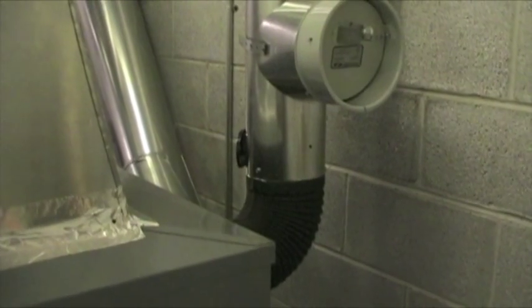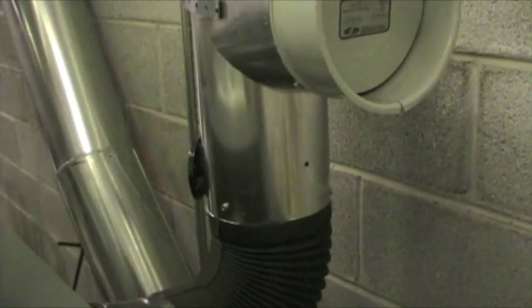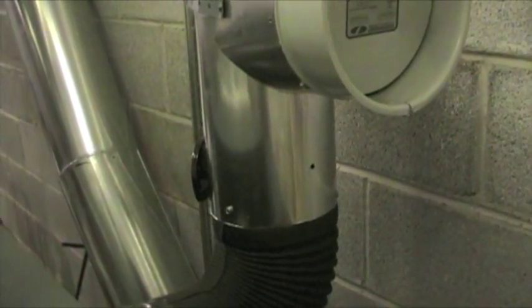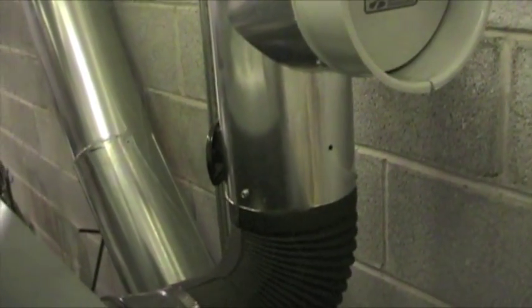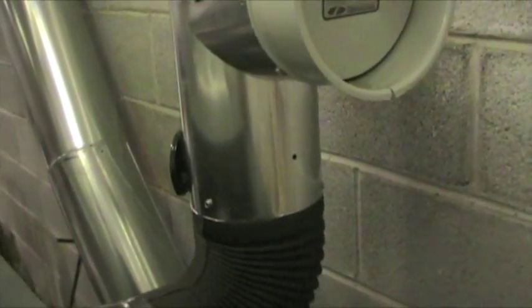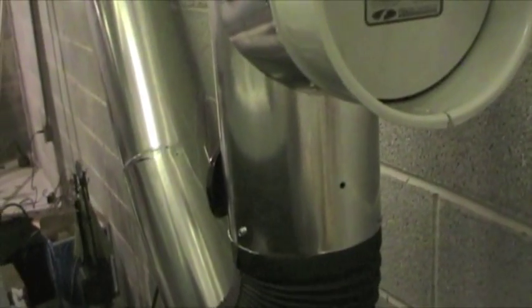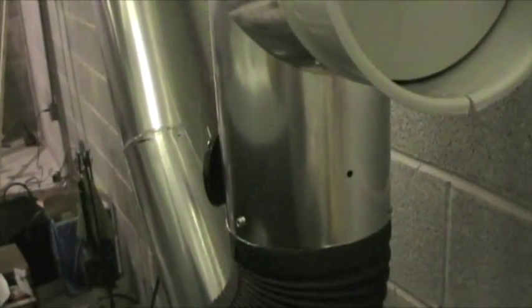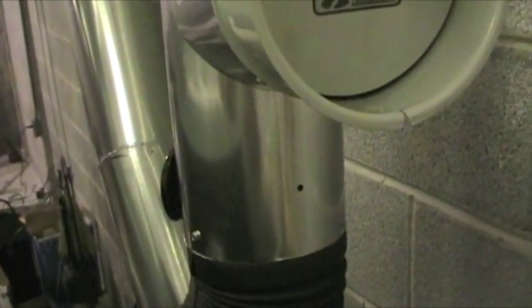The draft is supposed to be set for minus 0.03 inches water column. I can't get mine that low—I don't know whether it's my altitude or setup or what.